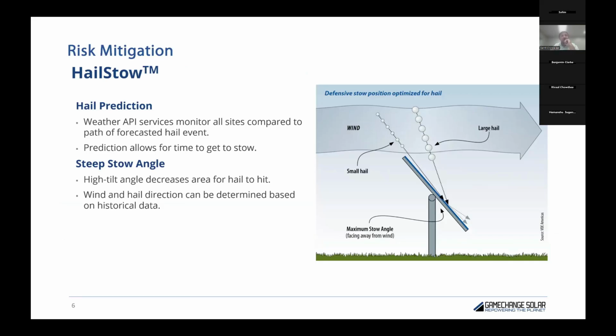Our solution to this is hail stow. We specifically use a prediction system for hail, not on-site sensors, because by the time sensors are hit on site, it's already too late, you've lost half your plant to hail damage. We continuously monitor the weather state around sites in both a 30-minute and a 15-minute interval, and then give a command to stow the trackers. In that sense, we are able to reduce the perceived risk that a lot of these sites have, which is one more card we have on the finance side: in the long run, can we reduce risk?